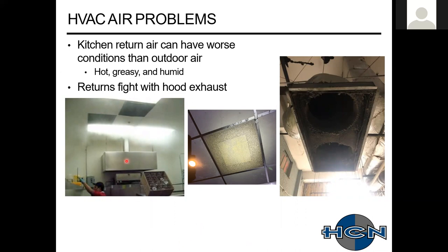The reason for that is a lot of that air in the kitchen space, especially in a dish room, I've seen people put returns in dish rooms. It's very hot, humid. That air is just going to get pulled right into that rooftop unit. And if that rooftop unit is not sized accordingly for that, it's not going to perform properly. And you're going to have a system that's fighting itself all the time.